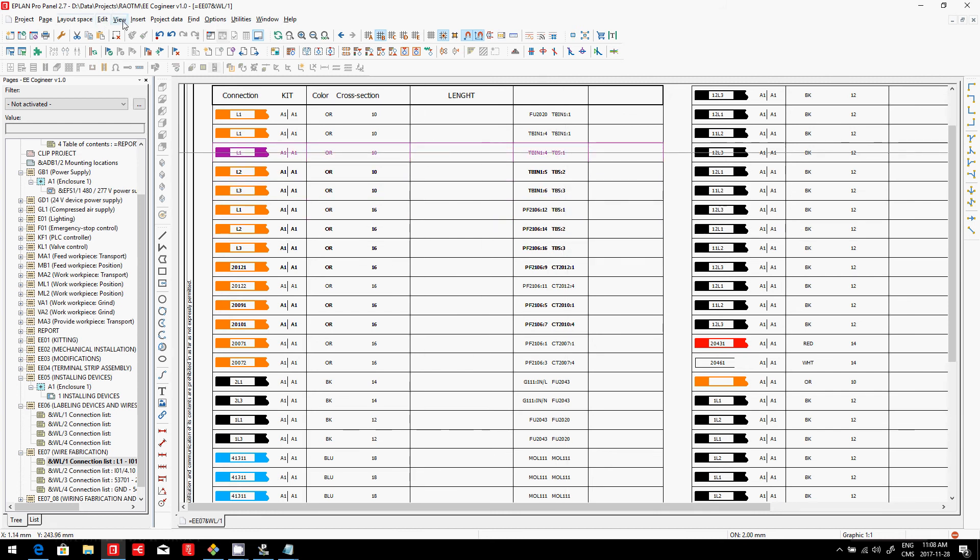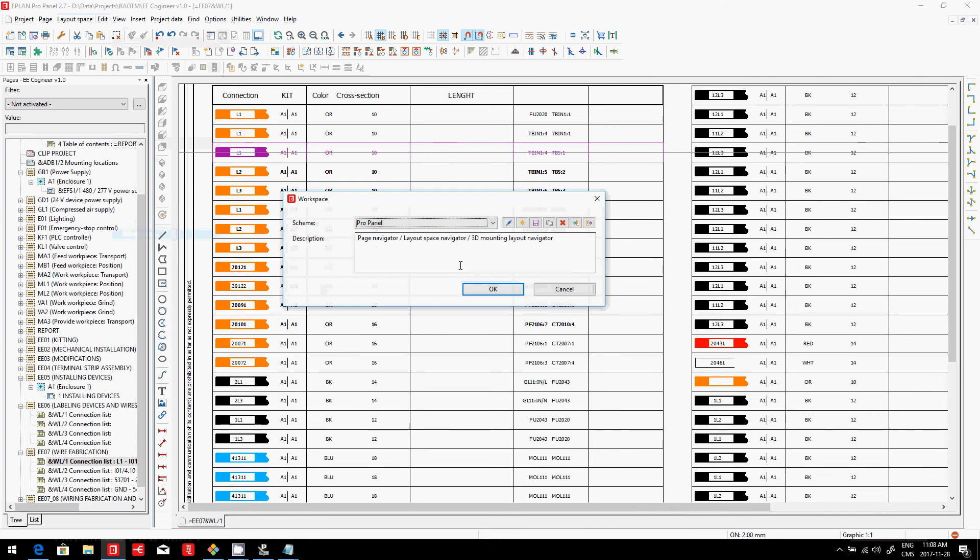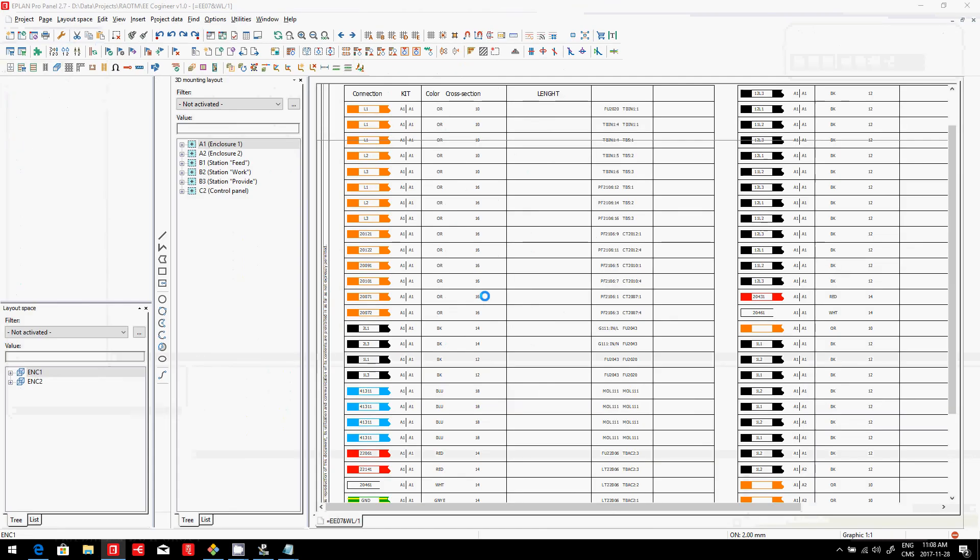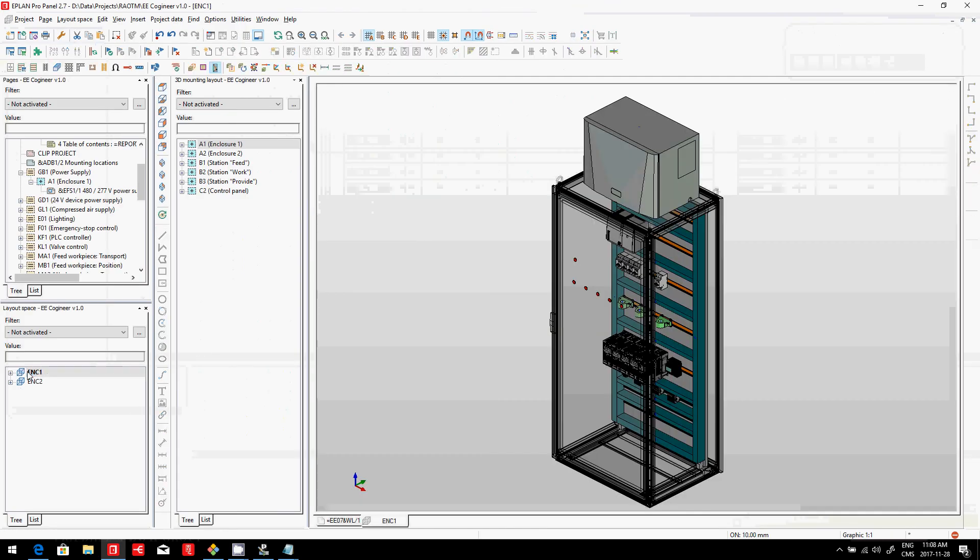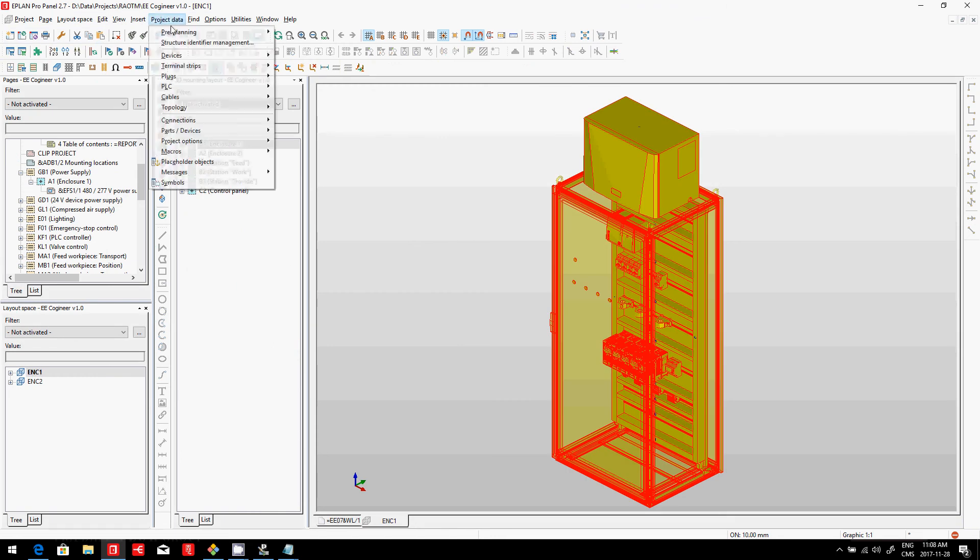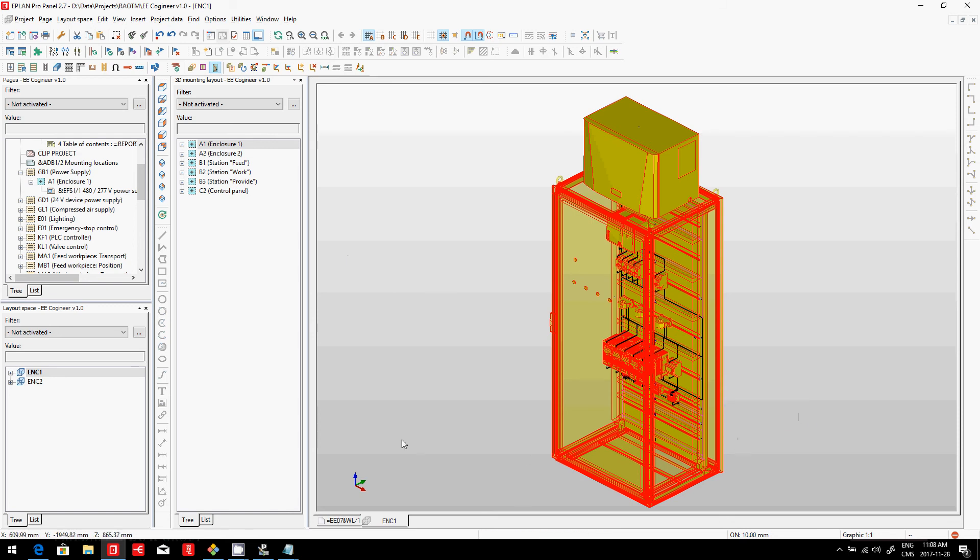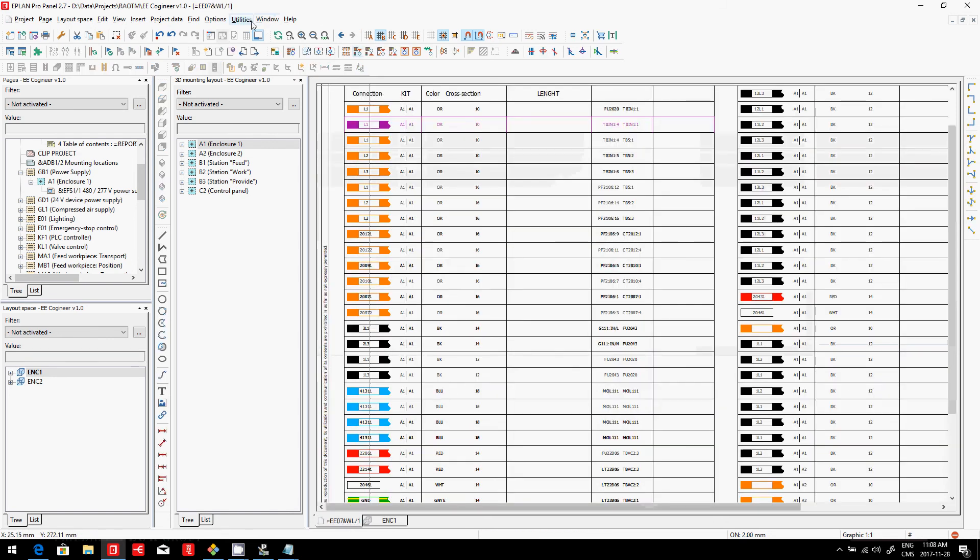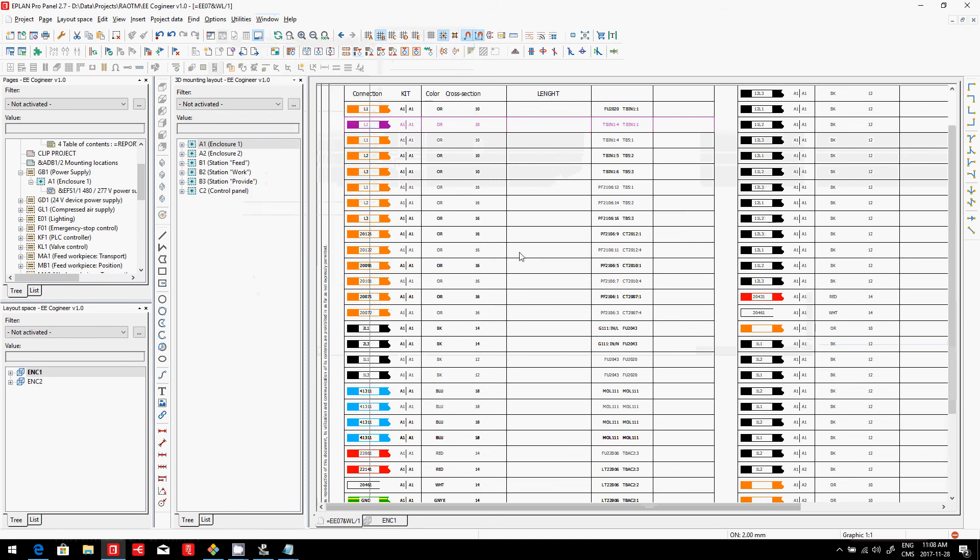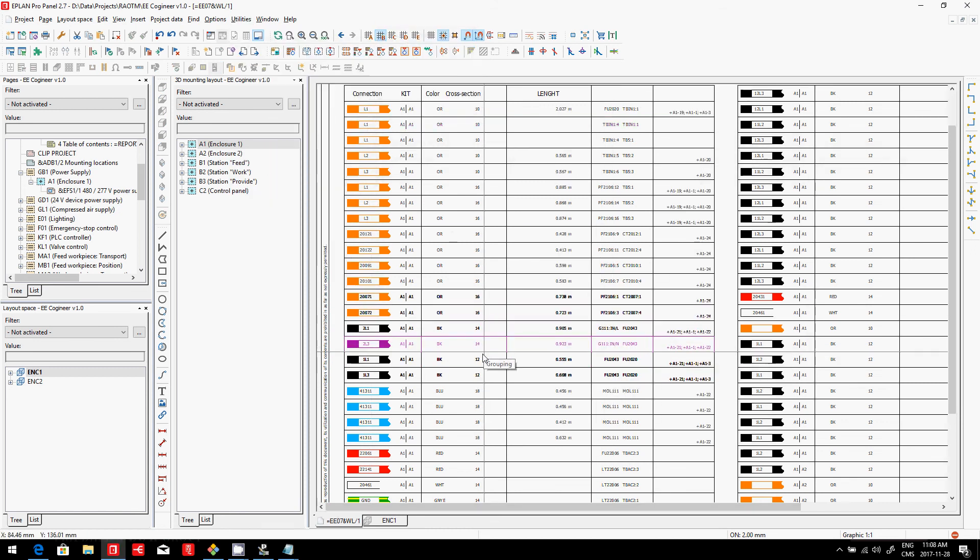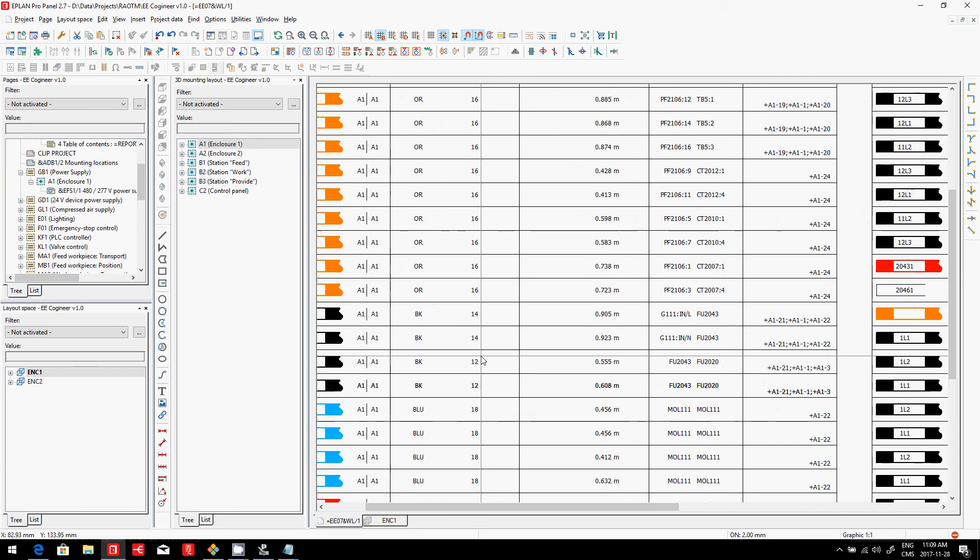Where does the length come from? Well, if we go back to our pro panel here, we have our enclosure. Inside this enclosure, when I take a look at this, I have all my devices positioned. Now, I can route them. When I route them, you see these wires appear. And from that point on, your wire list, if you just update it, you will see length appear in every one of these wires that is on that particular panel.